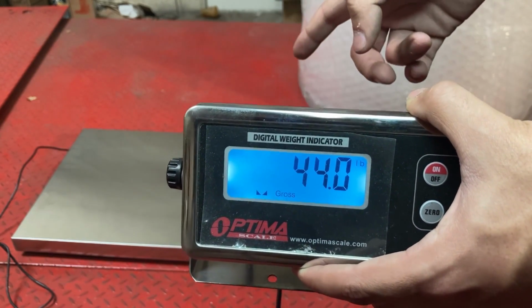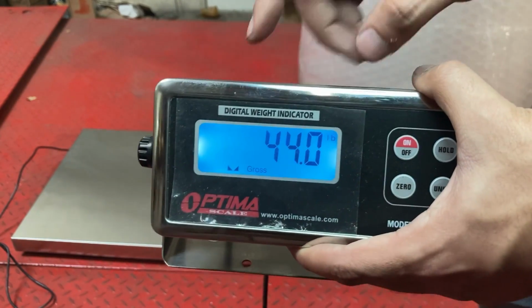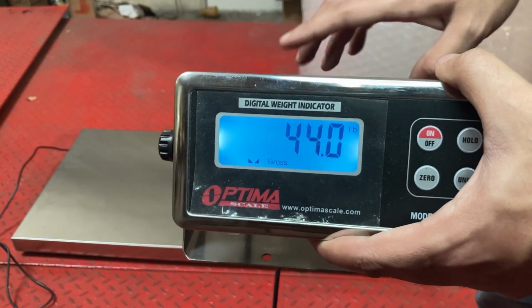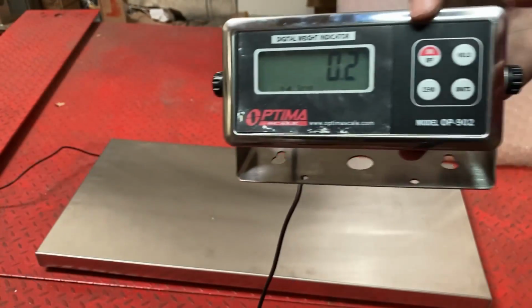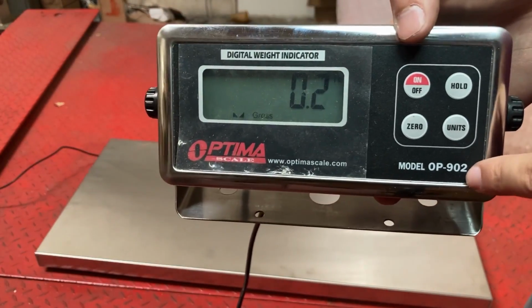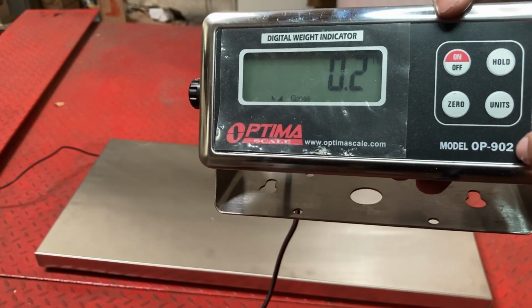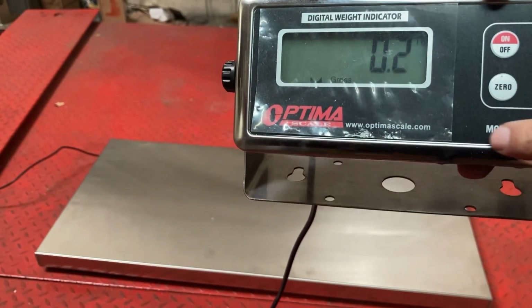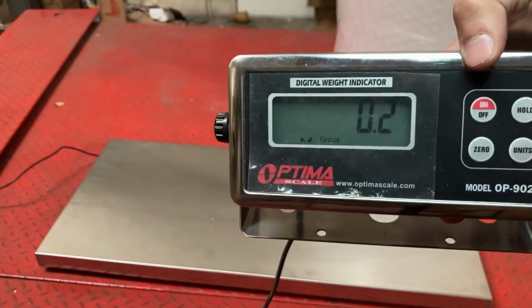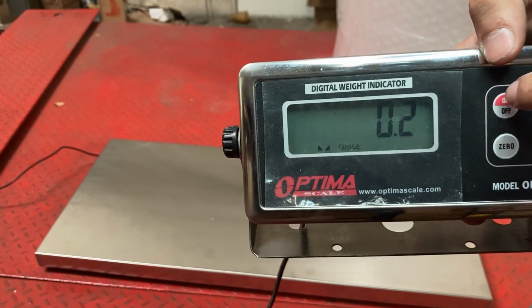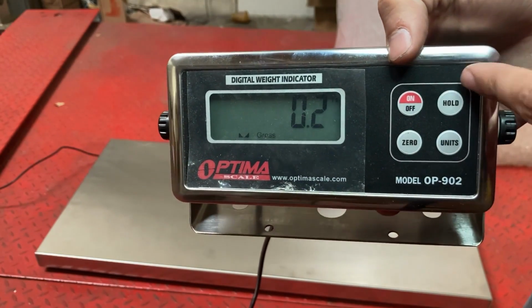So next we're actually going to check the junction box. Because for some people, this calibration and checking the feet did not fix the problem. One thing I wanted to mention about the 902 is that I've noticed, maybe after a couple years of usage, maybe 2-3 years, sometimes they fail. Meaning, no matter how hard I press the on-off button, they do not turn on.